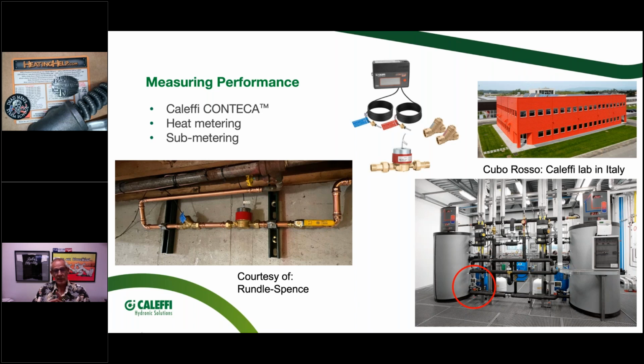I had it on my solar tank, and in the winter months my solar tank would only get up to 120 degrees. So I went to what's called a close approach method, and Siggy helped me size it. A close approach means I want my B side, the domestic water coming out, to be pretty close to 120 degrees. I don't want it much colder than that for domestic hot water.